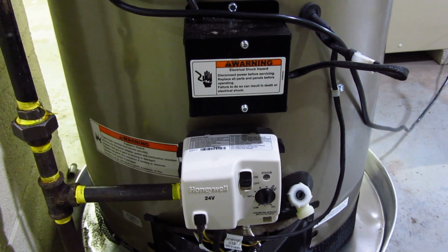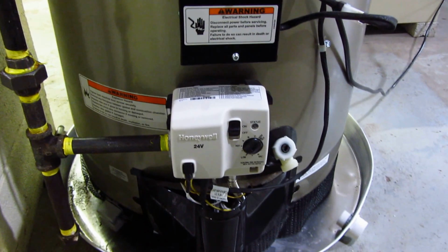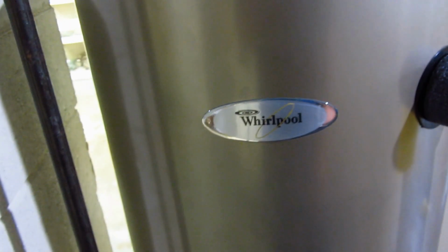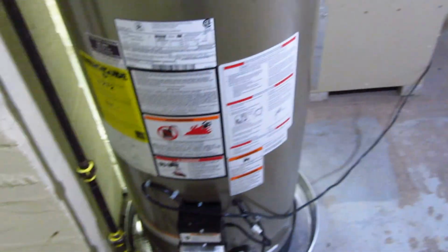The only thing we've had a problem with is it backdrafts because this is an old house. It's not ready for a high efficiency unit, so we have to work on that. But I turned it on very hot. Evidently it's not really calling for that.